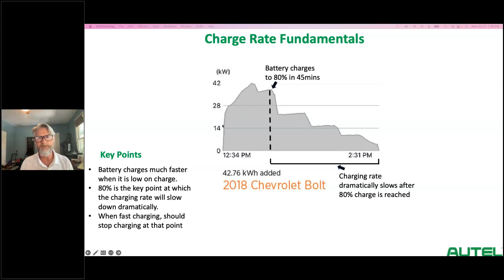So back to some simple math, and I promise this is the end of the math, but let's do the same thing we did earlier. The time to charge with DC, right? We get rid of all that acceptance rate stuff. So let's say I have a 40 kilowatt DC charger, 60 kilowatt battery. If I'm doing a full down and up, like 0 all the way up to 60, then it would only take 1.5 hours. But as I just explained, you're typically just going to go up to the 80%, and you can get there usually in less than an hour.